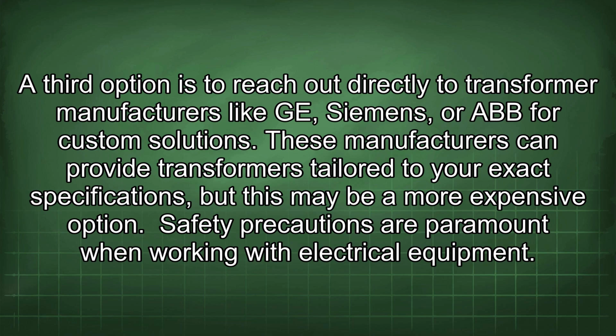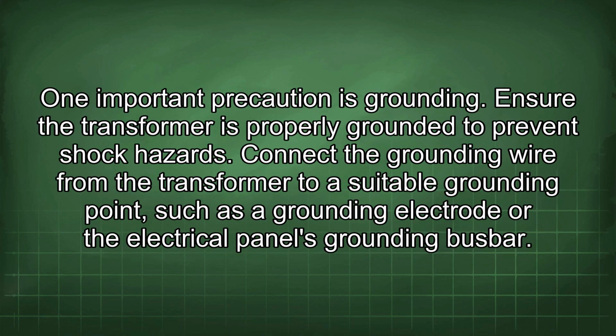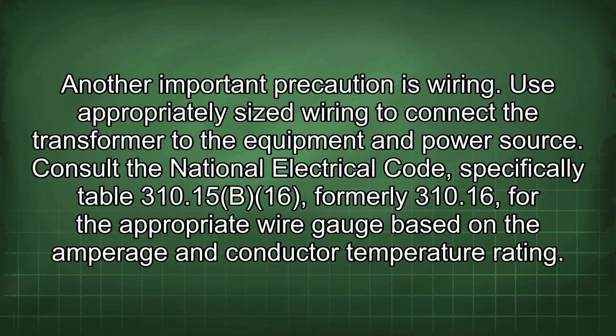Safety precautions are paramount when working with electrical equipment. One important precaution is grounding. Ensure the transformer is properly grounded to prevent shock hazards. Connect the grounding wire from the transformer to a suitable grounding point, such as the grounding electrode or the electrical panel's grounding busbar. Another important precaution is wiring.